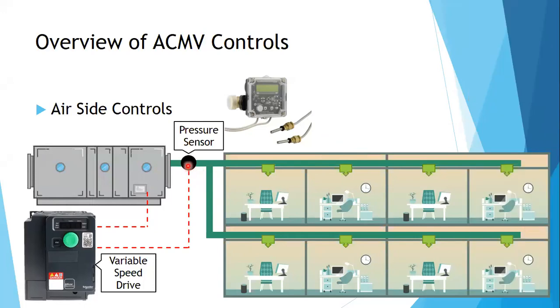Oh, where are we? So this pressure sensor, for example, this room closed down. This pressure sensor will go up. The pressure sensor senses an increase of pressure, telling this variable speed drive to lower down or speed down, so that the volume of air will be lowered down, maintaining your pressure set point. Okay.